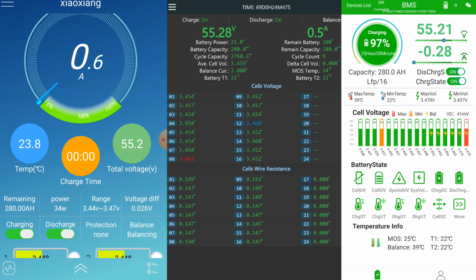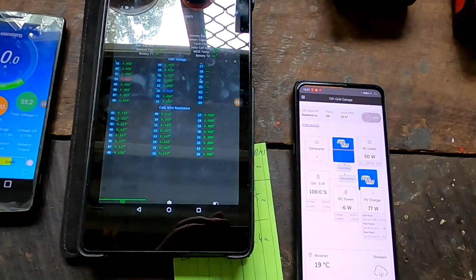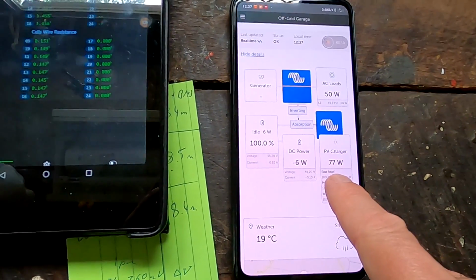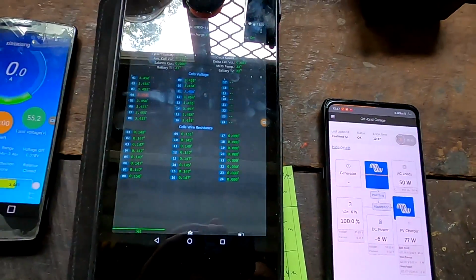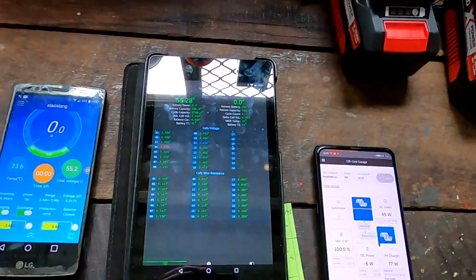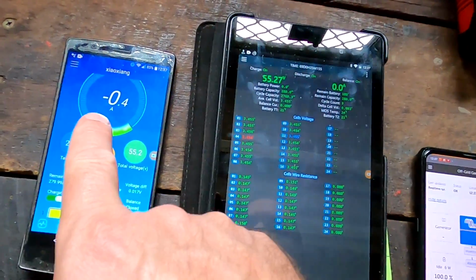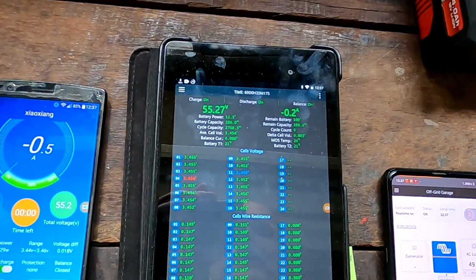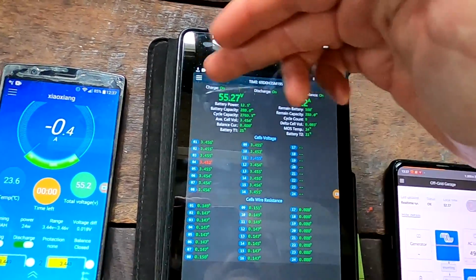The batteries will stay at 55.2 volts as long as you have set the absorption time. Now the solar charge controllers have throttled down to 77 watts only, maintaining the standby power of the garage here, and there's no current going into any of the batteries anymore. They're just hovering at 55.2 volts, balancing.